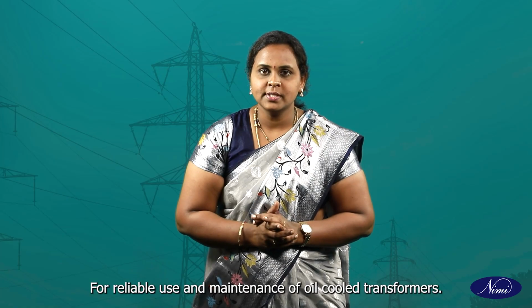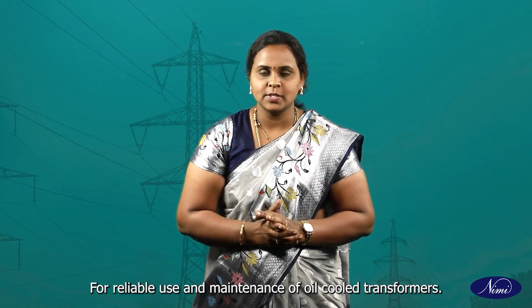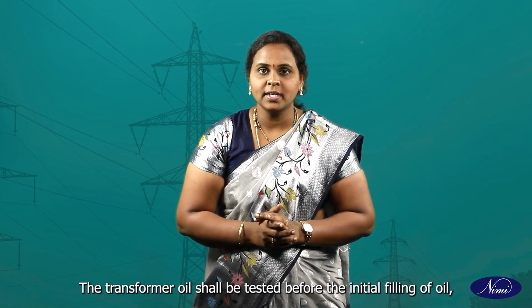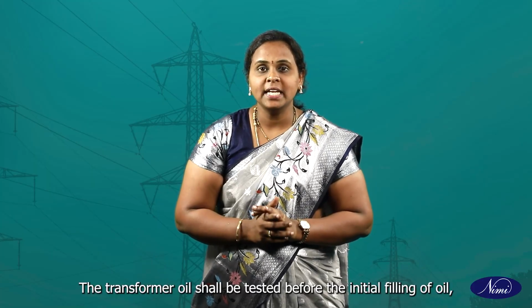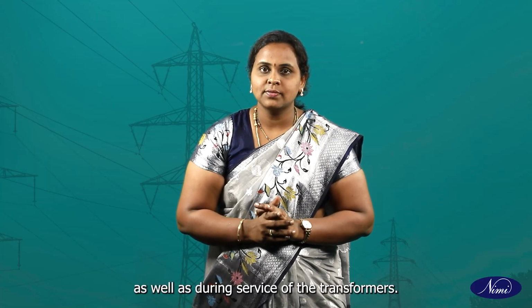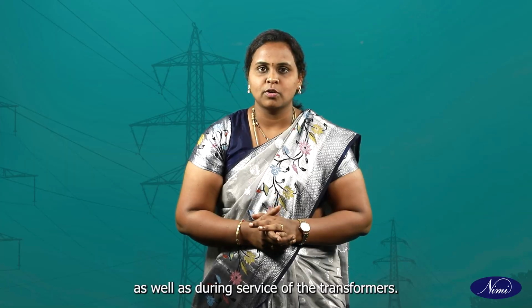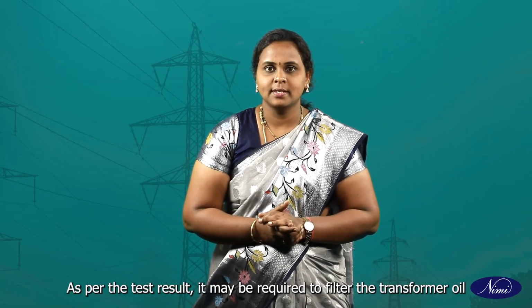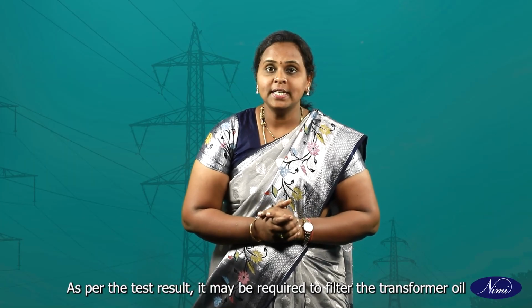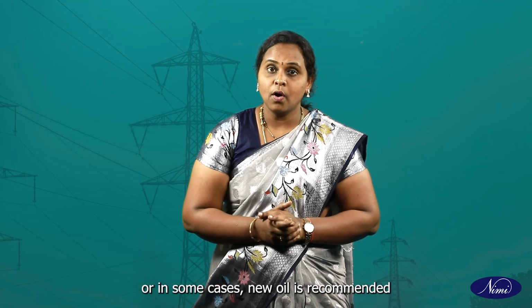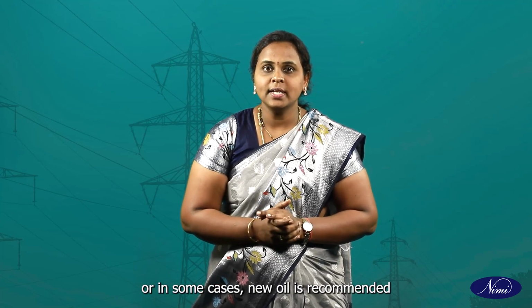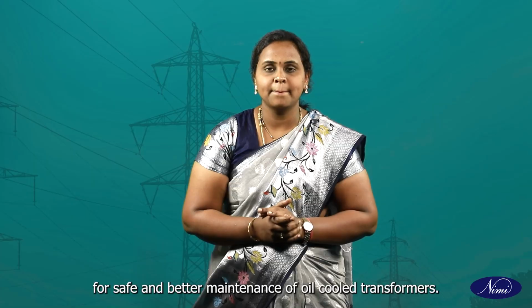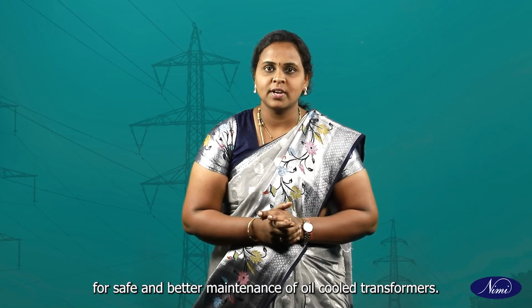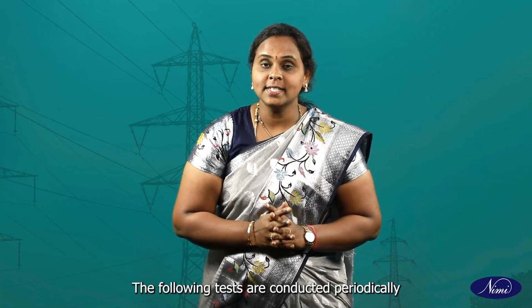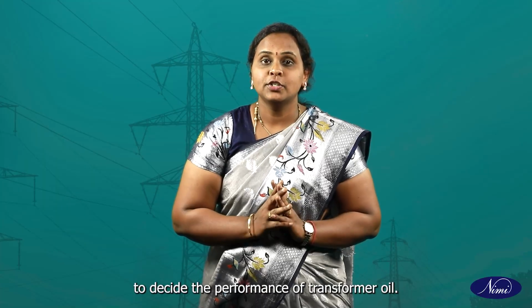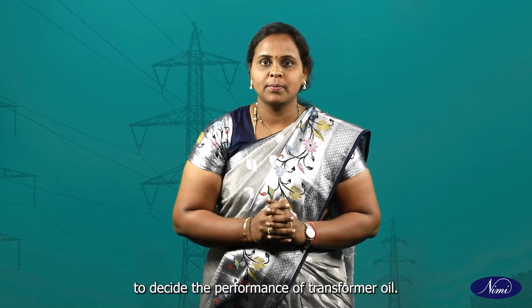For reliable use and maintenance of oil-cooled transformers, the transformer oil shall be tested before the initial filling of oil as well as during service of the transformers. As per the test result, it may be required to filter the transformer oil, or in some cases, new oil is recommended for safe and better maintenance of oil-cooled transformers. The following tests are conducted periodically to decide the performance of transformer oil.